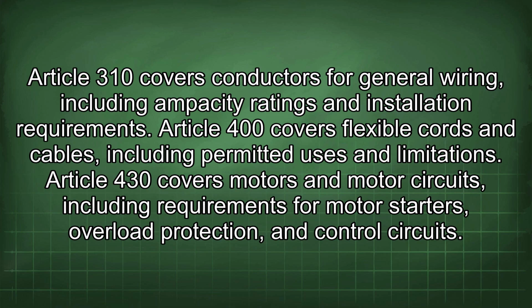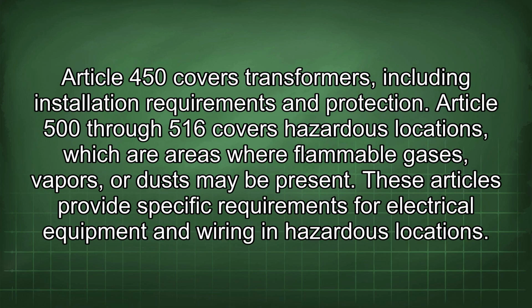Article 430 covers motors and motor circuits, including requirements for motor starters, overload protection, and control circuits. Article 450 covers transformers, including installation requirements and protection. Articles 500 through 516 cover hazardous locations, which are areas where flammable gases, vapors, or dust may be present. These articles provide specific requirements for electrical equipment and wiring in hazardous locations.